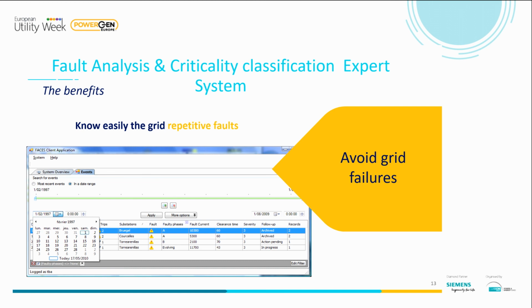They realized that on a specific segment of the grid, they had changed one cable, and this cable didn't have the same reaction to the wind as the two others. So with the wind, they had a transient fault. They reduced the span of the two other cables and solved the problem. No more stress for this breaker.